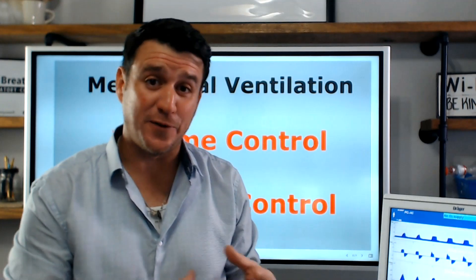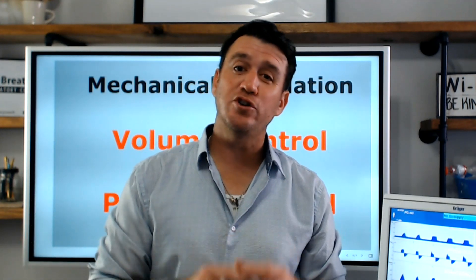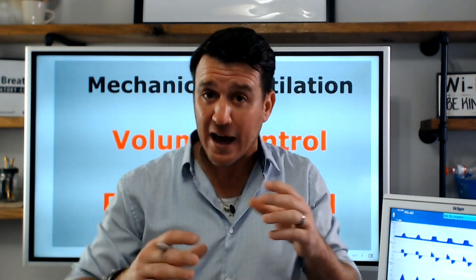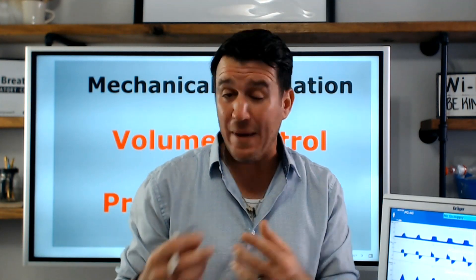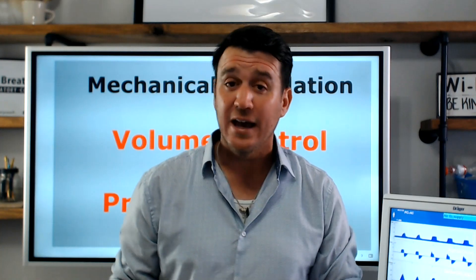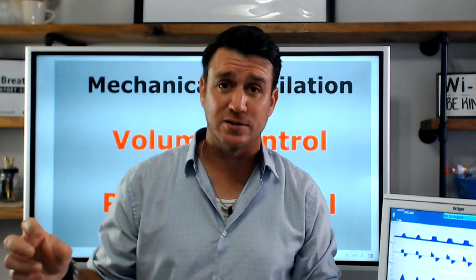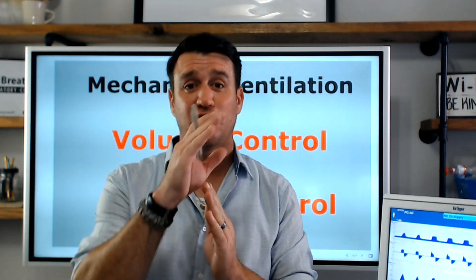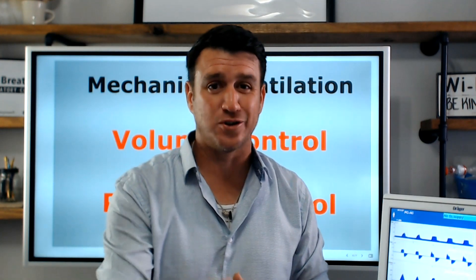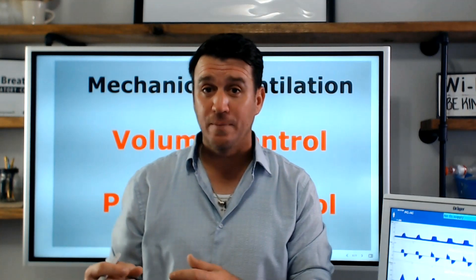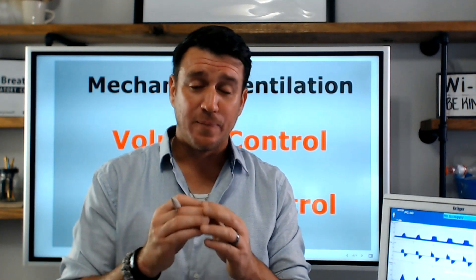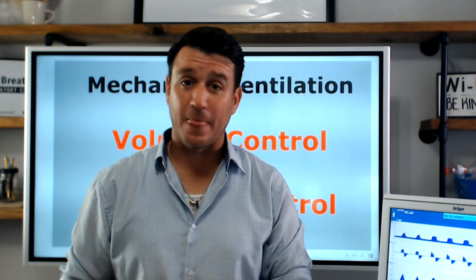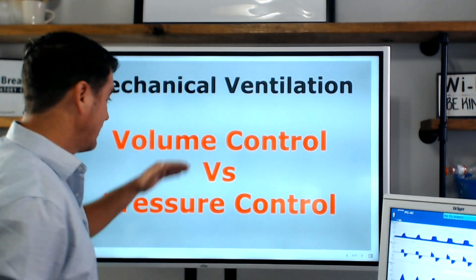So there you have it — that's volume control versus pressure control when utilizing waveforms to determine which mode you are in. Remember, volume control is always going to have either a constant flow pattern or a decelerating flow pattern, depending on your ventilator. But the key is the pressure waveform — you're always going to see this slow rising pattern. Remember: as volume goes, pressure grows. When talking about pressure control, you will always have a square pressure waveform and always a decelerating flow pattern. Always. That's the difference in volume control versus pressure control.